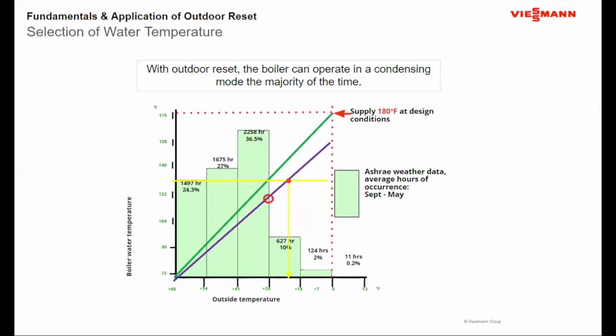In fact, let's tie in a couple of points here, back to the previous slide about the generic efficiencies. This point right here, which represents about 120 degree return water temperature. With 120 degree return water temperature, that represents about 90% efficiency. So that boiler that's not efficient on design day will be 90% efficient for about 88% of the heating season.